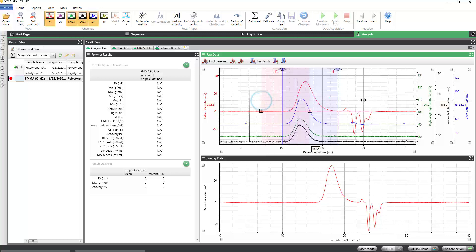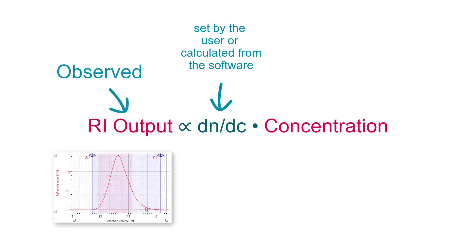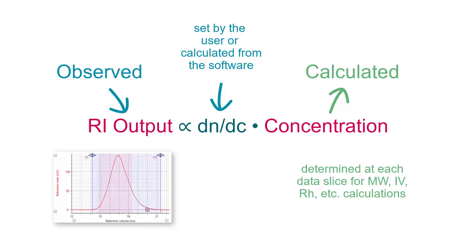These options exist to allow the user to choose how the associated dn/dc value is set or determined. Utilizing a dn/dc value unlocks the software's ability to calculate the sample concentration at each data slice, further allowing the calculation of absolute molecular weight, intrinsic viscosity, and other molecular parameters.